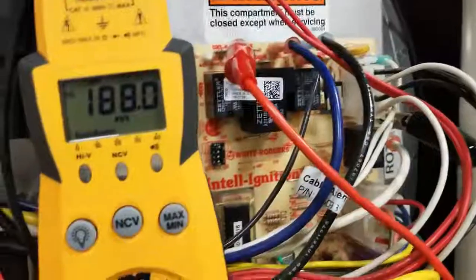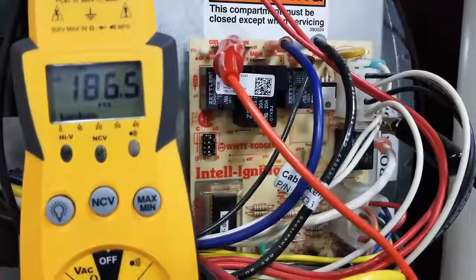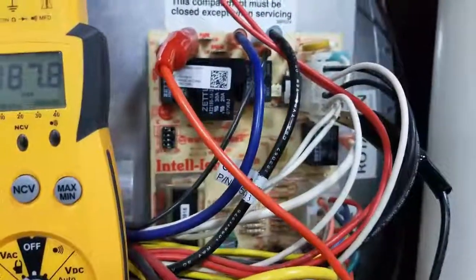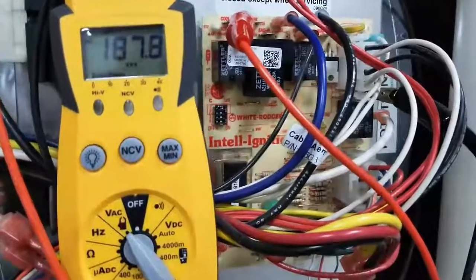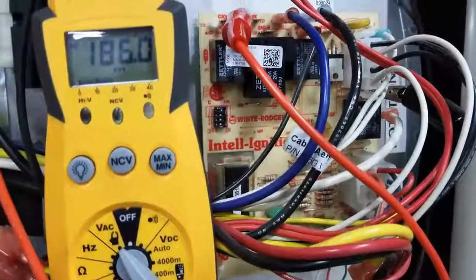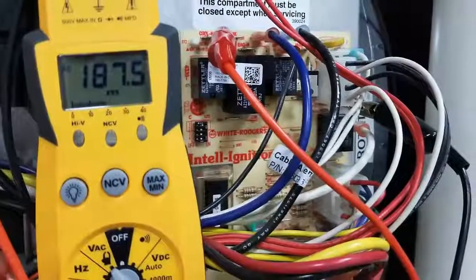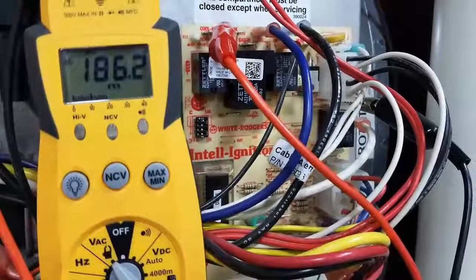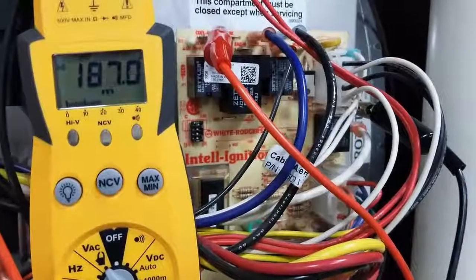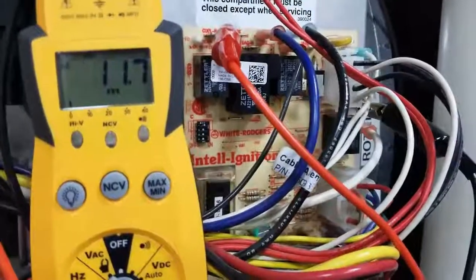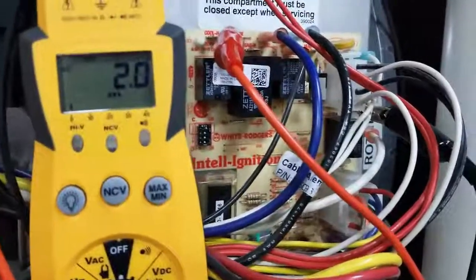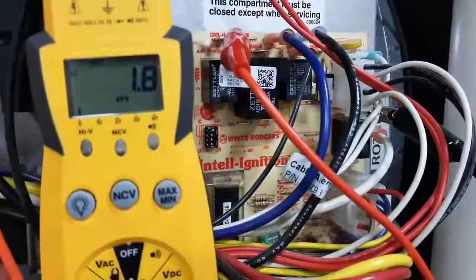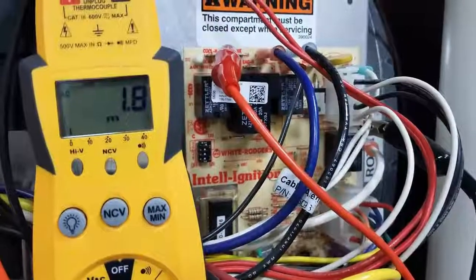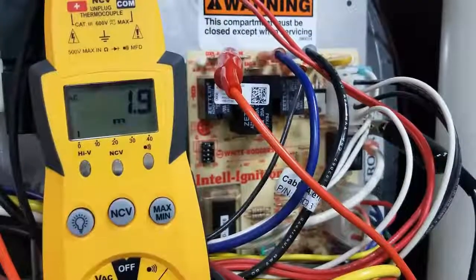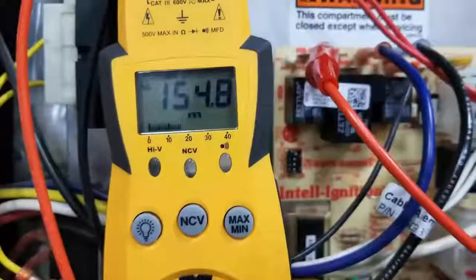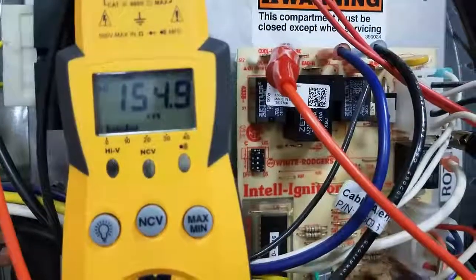Right now the power is off, so we're just seeing some slight millivoltage. It's just residual voltage. I'm going to go ahead and flip the power on, and the furnace is calling for heat. And what we're looking for now is to see if we're going to get 120 volts from the circuit board to the fan. Now the inducer's got to run, the igniter's got to start, the gas valve's got to fire. So this can take about 60 seconds before you're going to get power to the fan. Okay, inducer motor started up.